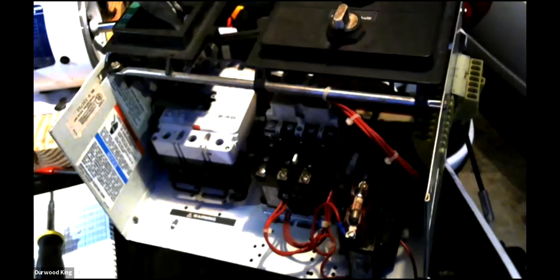Now those part numbers are like an X21 or X whatever. It's going to tell you how many amps that overload would actually be calibrated for. It's a fixed overload. Let's take a look at what a fixed overload looks like on a starter instead of an adjustable overload. So I'm going to cut the screen share off so I can see what I'm doing with the camera. And I'm going to show you.